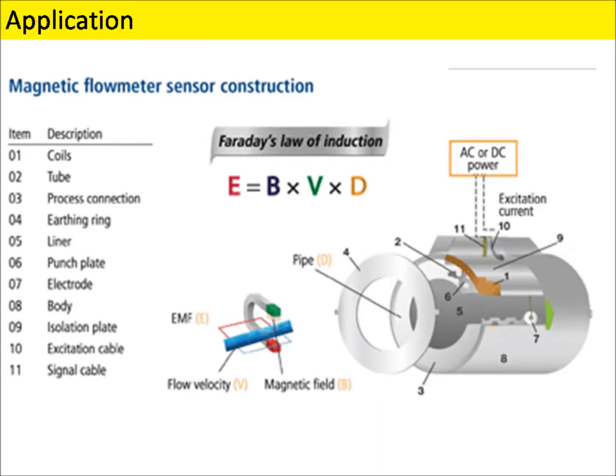Magmeters are highly scalable, running from 0.1 inch to 104 inches or more in diameter. They work well for clean fluids, such as water, acids, and caustics, or in heavy particulate applications, such as paper stock, pulp, and lime slurries. As mentioned earlier, the main requirement is the process media must have some level of conductivity, with a typical minimum range of 1 microsiemens to 5 microsiemens. As long as the process meets this requirement, the meter should perform satisfactorily in the application. Most oil-based liquids are not conductive, which knocks magmeters out of many refinery applications.